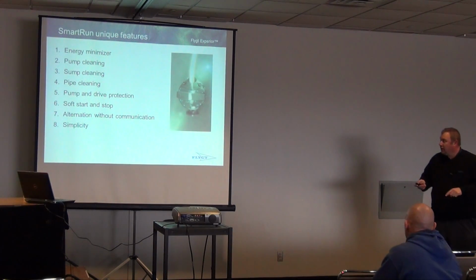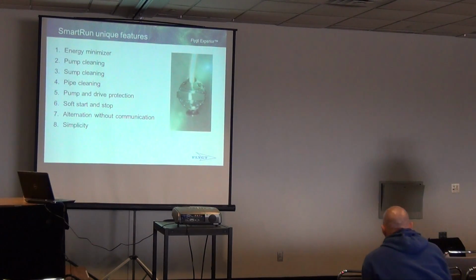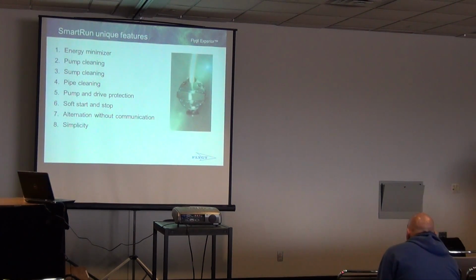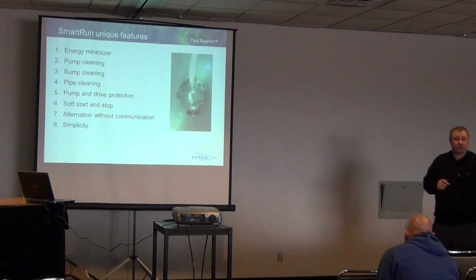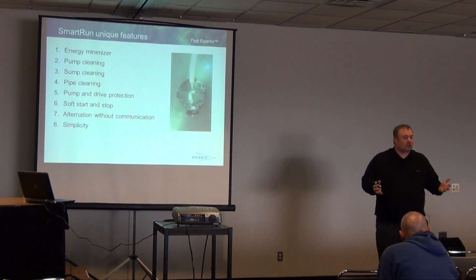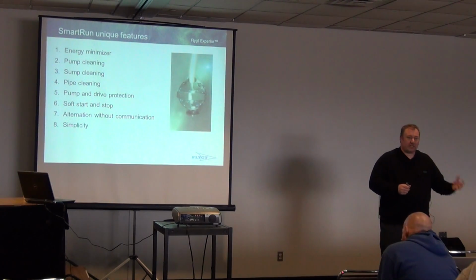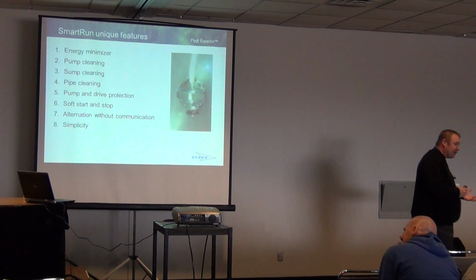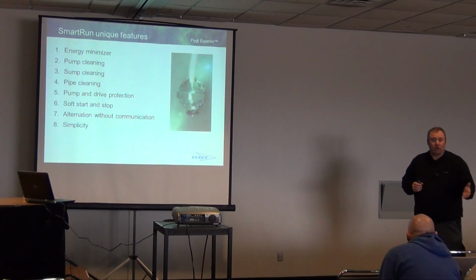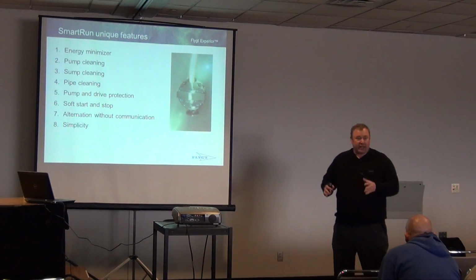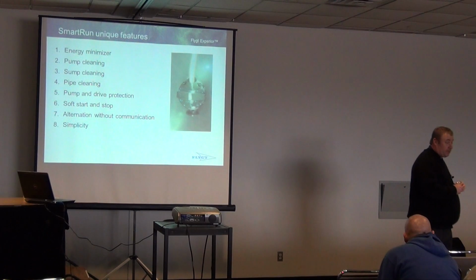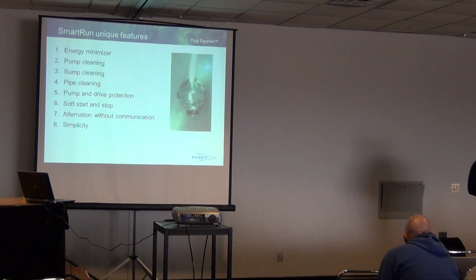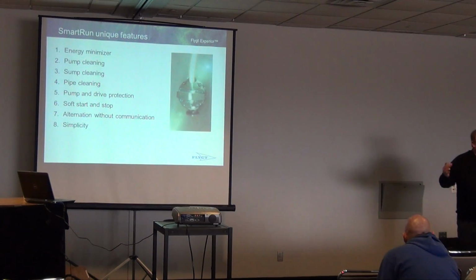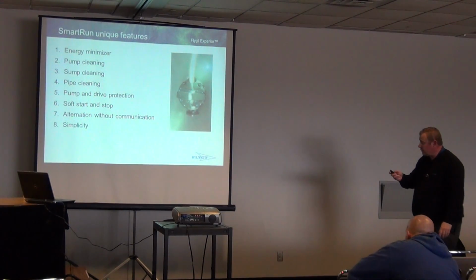And it will tell you that with the functionality of a smart run controller and hydraulics, with a high efficiency motor, all three of those things, or mix and match however you would like, what kind of energy savings you can see at that specific installation with this equipment. So you would have an idea, and I just plugged one in today as I was working this morning. I plugged one in, a 60 horsepower unit running 1,500 hours a year at 7.5 cents per kilowatt, going from a channel impeller to an N impeller, and I calculated a $3,000 savings per year per pump at that horsepower. So it can be significant. And if you're running multiple pump stations throughout your community, that's the kind of savings compounded. You can see a lot of savings in the fact that you can get that payback on equipment quite quickly.